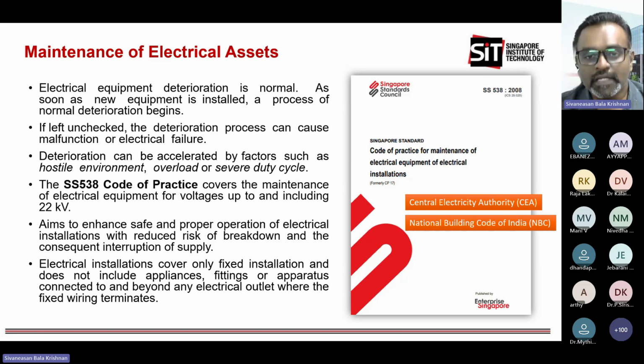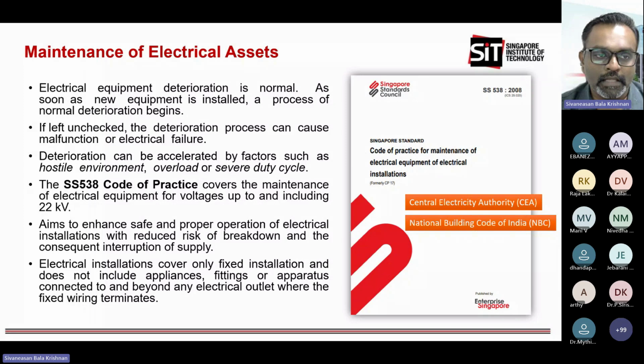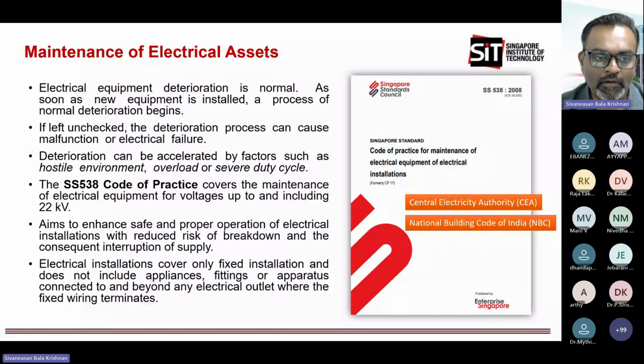This kind of activity can cause significant degradation in the operation or behavior of equipment. In Singapore, we have Singapore Standard 538, a code of practice covering the maintenance of electrical equipment for voltages up to 22 kilovolts. The idea is to enhance and ensure safe operation of electrical installations, aiming to reduce the risk of breakdown and interruption of supply. This covers fixed electrical installations, not temporary ones like at a fair, and does not include appliances, fittings, lights, and so on.